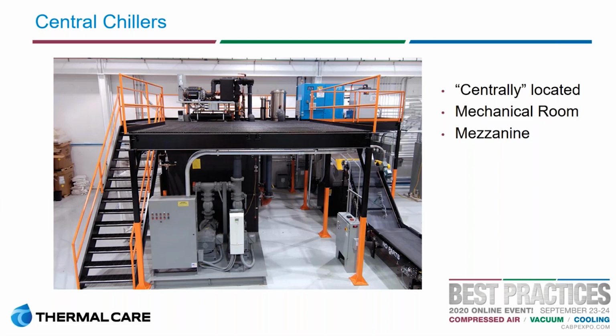That chiller uses refrigeration through a heat exchanger to remove the heat from that water. That water is now cold, leaving the chiller, and returns to the cold well of that tank. It then starts that process all over again with the process pump delivering it out. If you can imagine it, tracking the water is almost like a figure eight, where it goes out to the process, returns to the tank, up to the chiller, and returns to the tank to start over again.